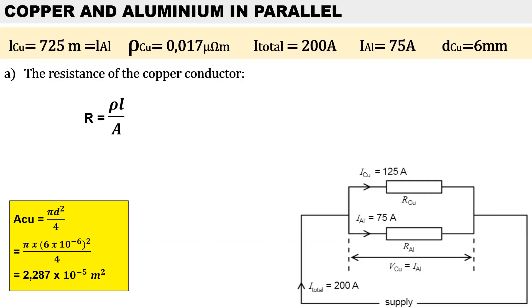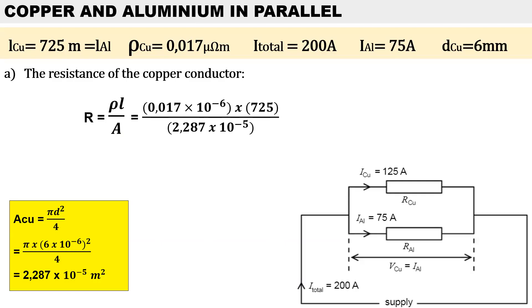Now we can calculate the resistance of the copper conductor. The resistivity of 0.017 micro ohm-meters — converted by multiplying by 10 to the power of minus 6 — multiplied by the length of 725 meters, divided by the area of 2.287 times 10 to the minus 5. Therefore, the resistance is 0.436 ohms.